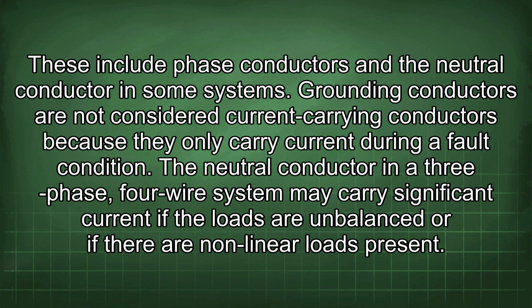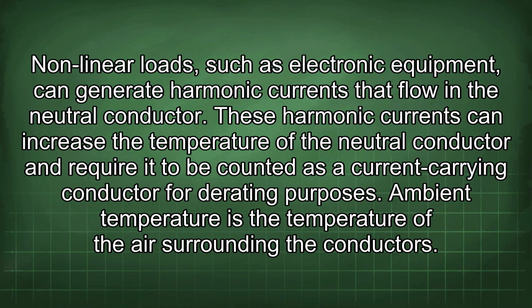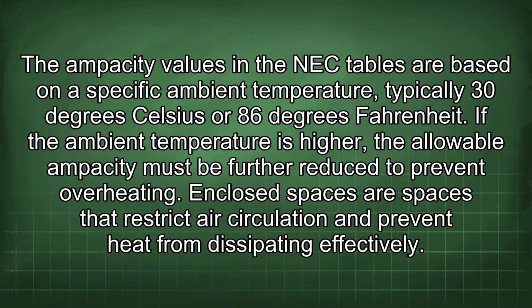The neutral conductor in a three-phase, four-wire system may carry significant current if the loads are unbalanced or if there are nonlinear loads present. Nonlinear loads, such as electronic equipment, can generate harmonic currents that flow in the neutral conductor. These harmonic currents can increase the temperature of the neutral conductor and require it to be counted as a current-carrying conductor for derating purposes. Ambient temperature is the temperature of the air surrounding the conductors. The ampacity values in the NEC tables are based on a specific ambient temperature, typically 30 degrees Celsius or 86 degrees Fahrenheit. If the ambient temperature is higher, the allowable ampacity must be further reduced to prevent overheating.